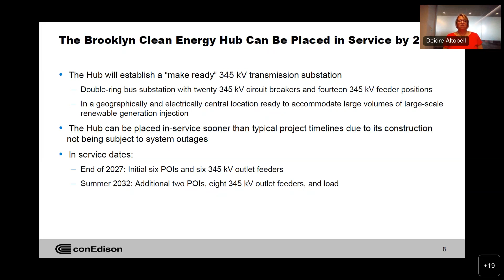The Brooklyn hub will enhance both system resiliency and reliability. Instead of constructing an open-air substation, the hub will be an enclosed building to protect equipment from a harsh weather environment. Storm hardening has also been accounted for by designing for a higher level of flood protection, 5 feet above the 2015 FEMA requirement. System reliability is also enhanced. By reconfiguring existing feeder connections and moving load from Farragut to the Brooklyn hub, Con Edison is diversifying the supply sources to customer load, which could help minimize the impact of an extreme contingency that could propagate throughout our system. As the system experiences load growth, whether it be organic growth or due to initiatives like electrification, the Brooklyn hub can be used to interconnect future load-serving stations.